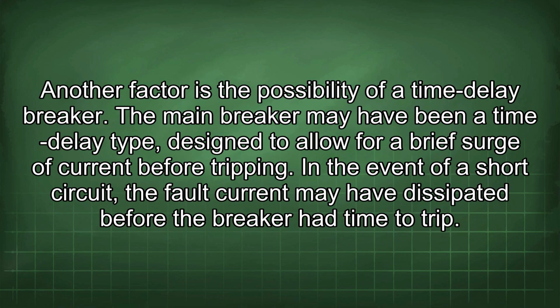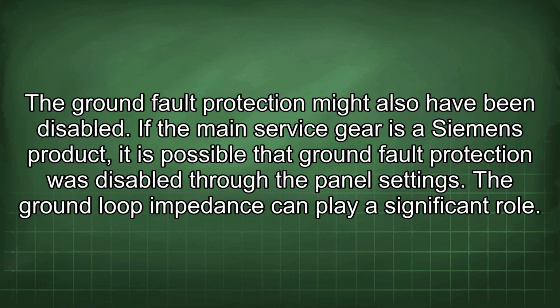Another factor is the possibility of a time delay breaker. The main breaker may have been a time delay type, designed to allow for a brief surge of current before tripping. In the event of a short circuit, the fault current may have dissipated before the breaker had time to trip. The ground fault protection might also have been disabled.